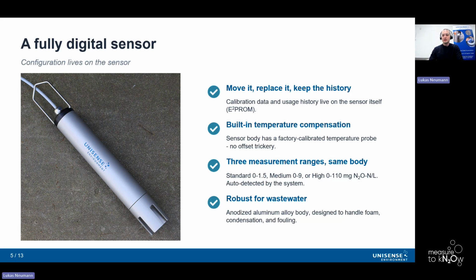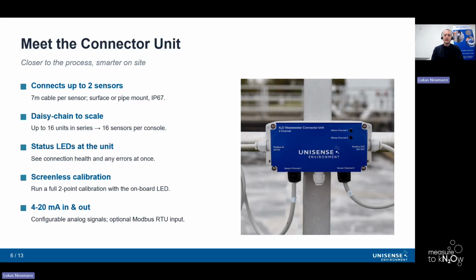As before, it has built-in temperature compensation for the three ranges, as seen previously: standard, medium, and high. The difference here is that the system auto-detects which type of sensor you've installed and then adjusts accordingly in terms of calculating the values. As before, the sensor body is built out of robust anodized aluminum and is made to handle the rough environments that are activated sludge. Then we have the connector unit, the new member of the family that didn't exist before.